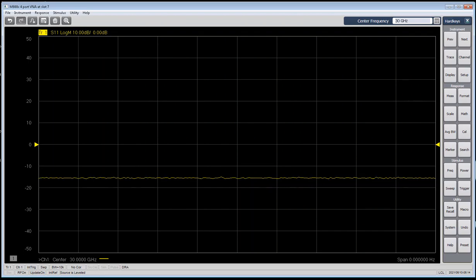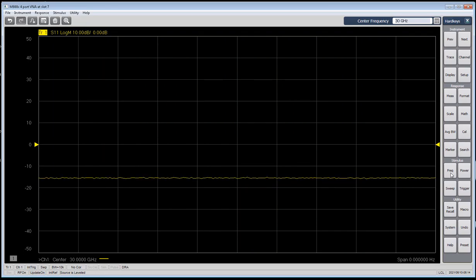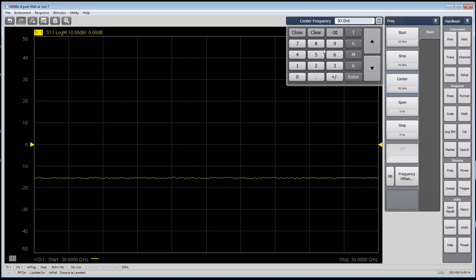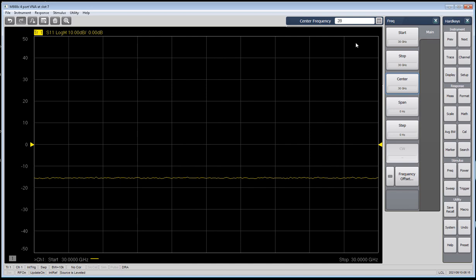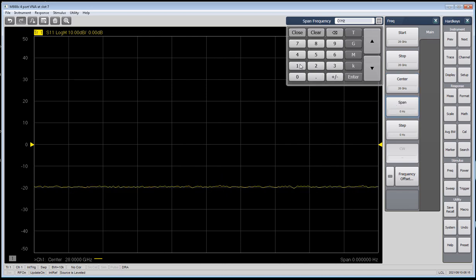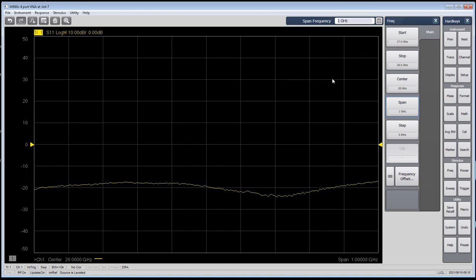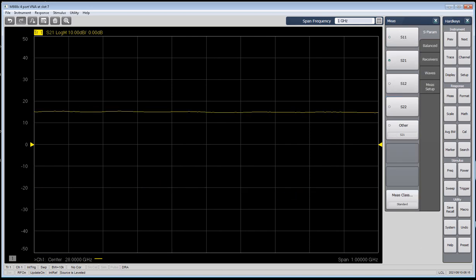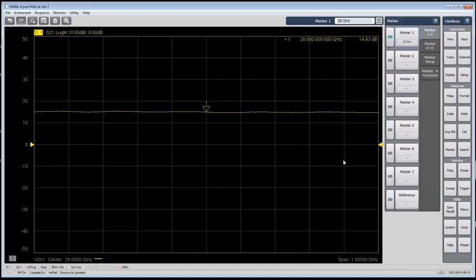I'm remoted into a unit on my computer, so let's get into the virtual demo. We're going to start by setting the frequency for our sweep. We're going to set a center frequency of 28 GHz, and then I'm going to set a span of 1 GHz, and that'll give us a good picture of the operating range of this amplifier that we're looking at. I'm going to change this to an S21 sweep, so we're looking at what's going through the amplifier. And then I'm going to turn a marker on, which will tell us the power level at the frequency that the marker is placed at.